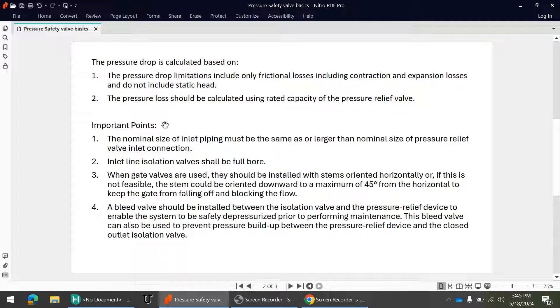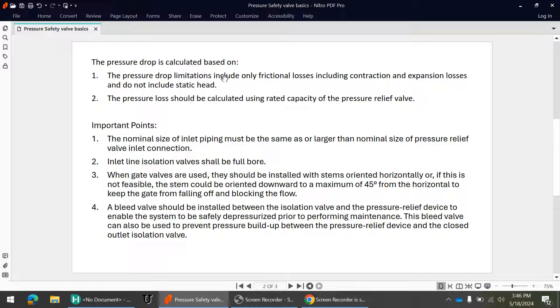While performing the pressure drop calculation, some basic terms need to be understood. The pressure drop limitations include only the frictional losses, which includes contraction and expansion losses and line losses. During inlet pressure drop calculation, do not include the static head. Also, the pressure drop should be calculated using the rated capacity of the pressure relief valve.